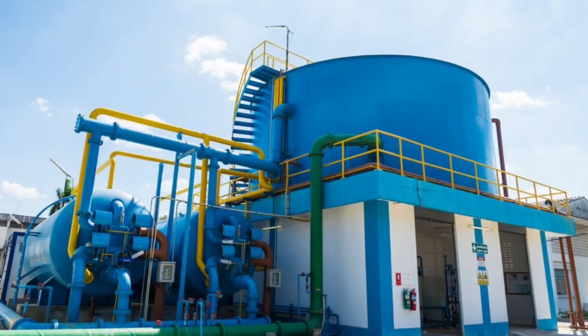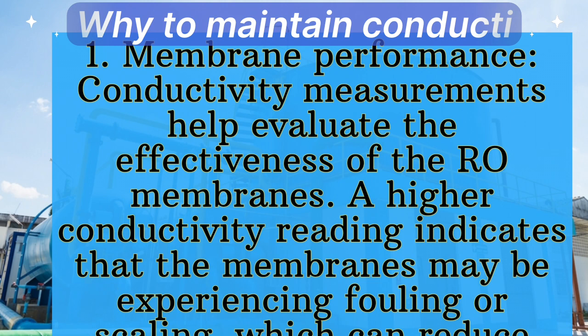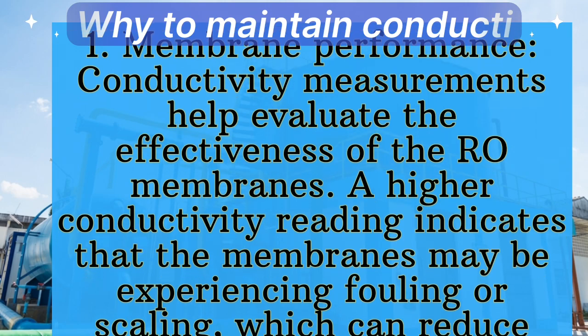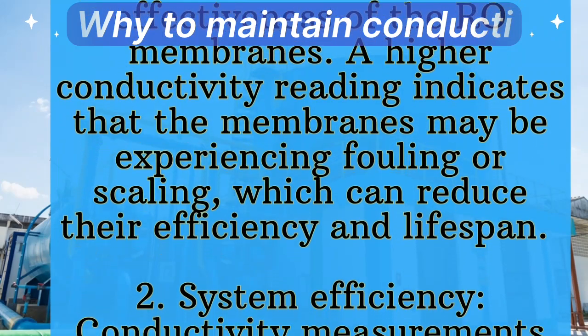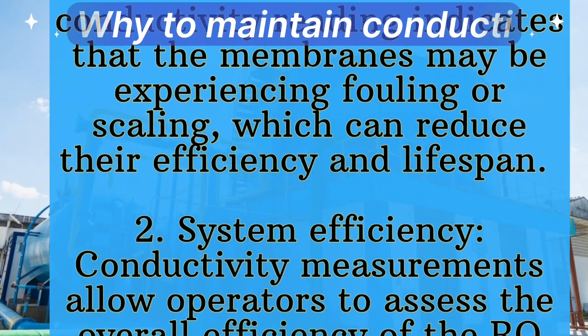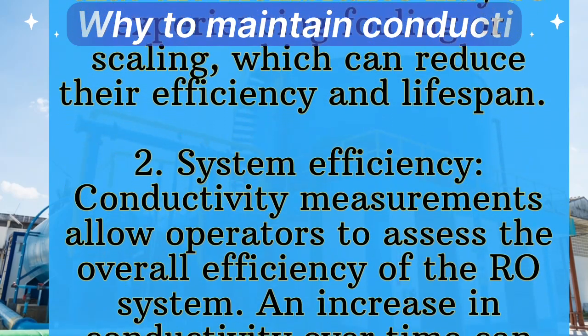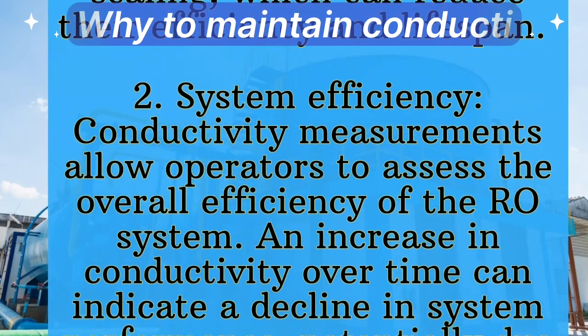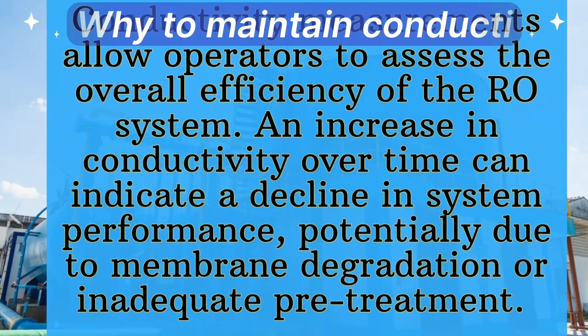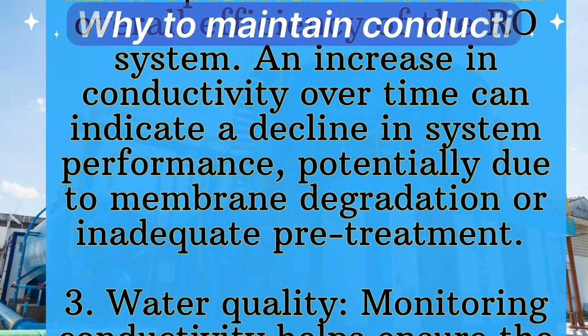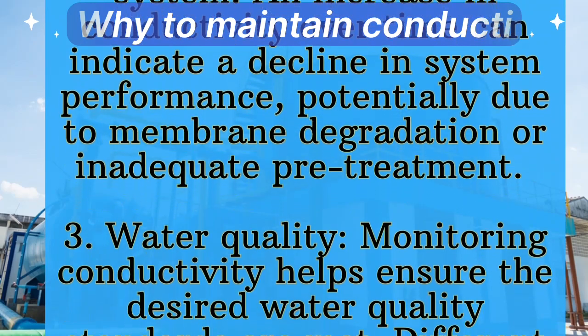In RO plant monitoring, water conductivity is important for several reasons. First, membrane performance: conductivity measurements help evaluate the effectiveness of the RO membrane. A higher conductivity reading indicates that the membranes may be experiencing fouling or scaling, which can reduce their efficiency and lifespan. Second, system efficiency: conductivity measurements allow operators to assess the overall efficiency of the RO system. An increase in conductivity over time can indicate a decline in system performance, potentially due to membrane degradation or inadequate pretreatment.